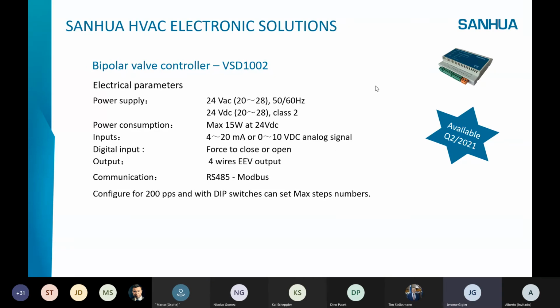So for this VSD, we have the supply with 24 volt AC or DC. The input, we have the same input. You can control it with 4-20 milliamp, 0-10 volt. You have also a digital input to force the valve to open or close. And we have four wires for the EEV output, and of course, the Modbus via RS485 port. This controller is configured for Sanhua valve, so for 200 PPS. This is the speed to open or close the valve. And with this switch, we can set the maximum number of steps, because we have seen before that it depends on whether you use a small valve 12 or 400, you don't have the same maximum number of steps.